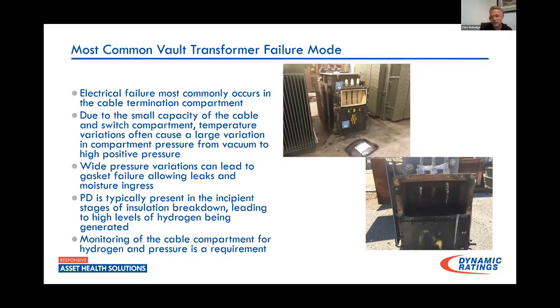This is really not that hard of a failure to detect. Typically, when you start seeing breakdown of these cables, there's usually a pretty good PD event prior to the failure actually happening, and that's easily detected through hydrogen monitoring. Again, PD monitoring would be great, but it's not really a cost-effective solution for this. So that was something else I took into consideration when we built our system for monitoring.